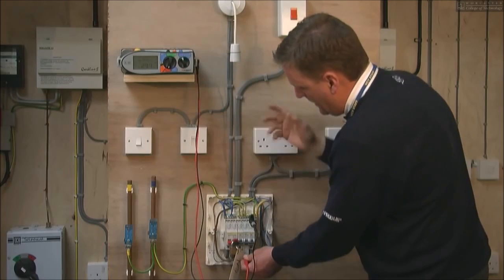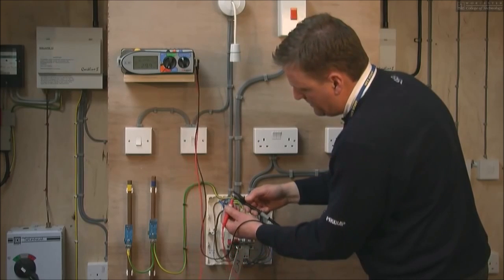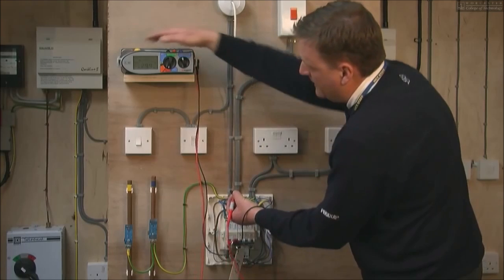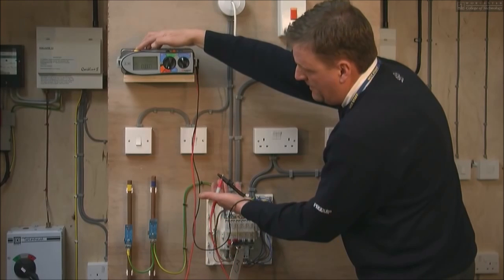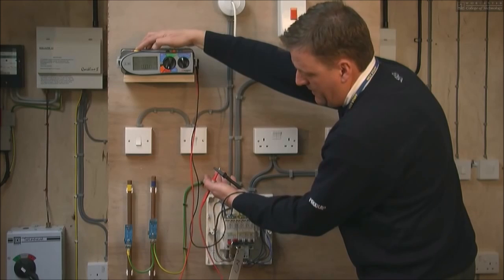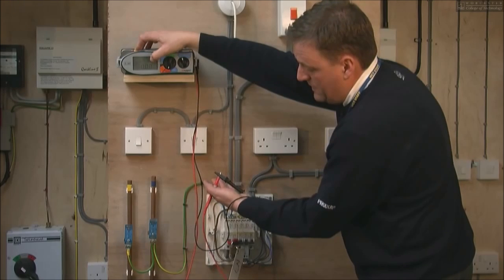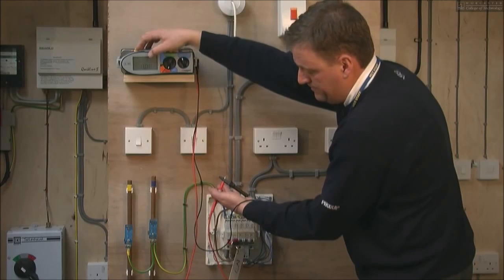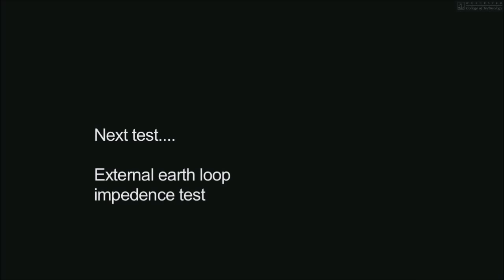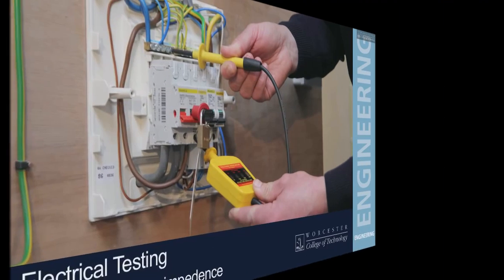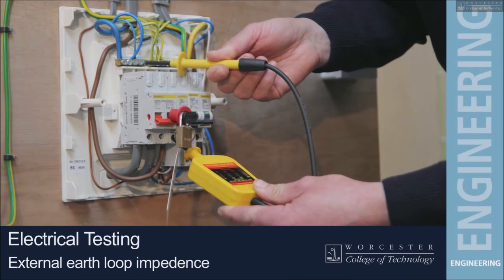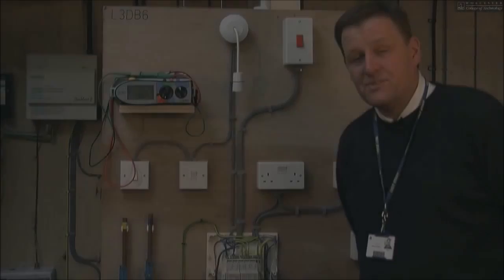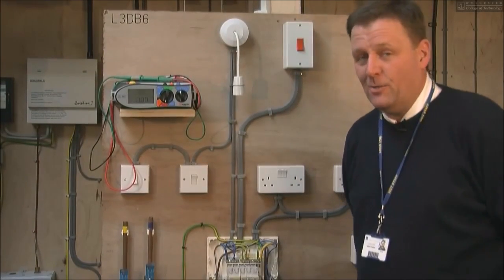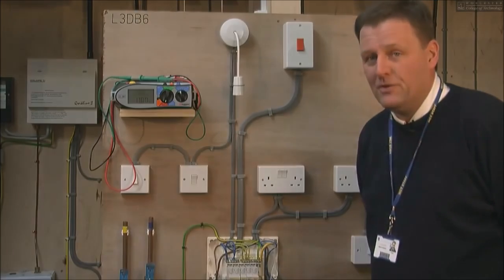Now if there was a fault in the circuit, and any of the conductors were touching, we would get this sort of reading. As you can see, I've got the two leads touching together. So anything that's reading this, there's obviously a dead short in the circuit or an earth fault potential. The next set of tests are live tests and should not be conducted at home unless you are fully qualified.